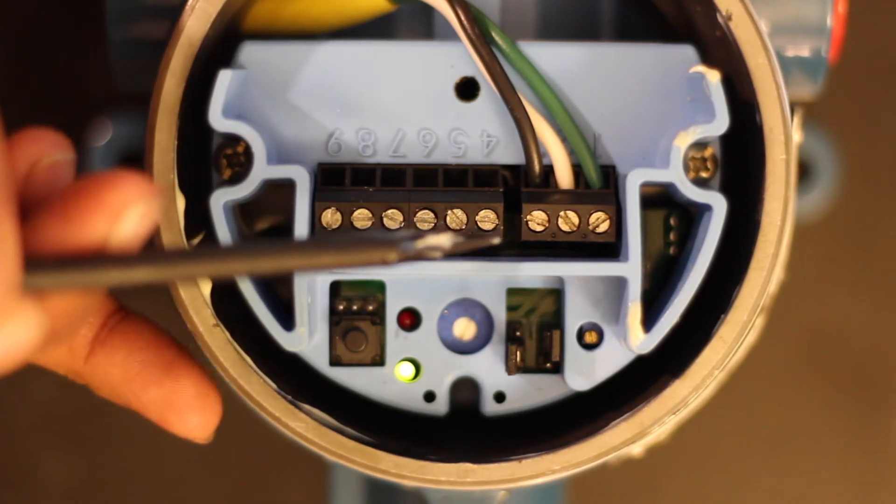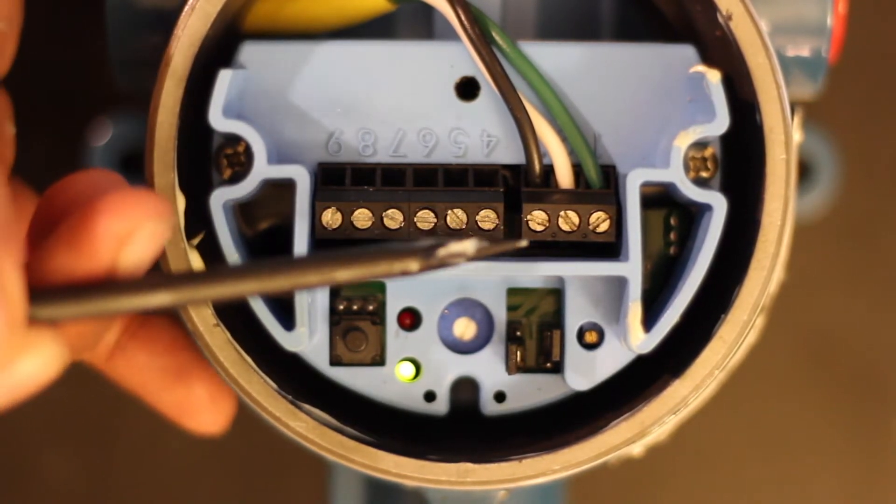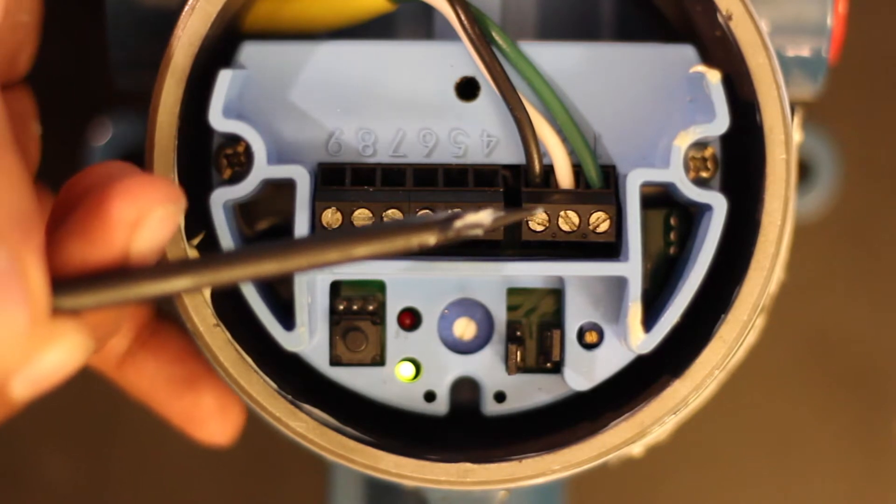You have your universal power supply connections. This particular unit will take in 24 volt DC, 120 volt or 220 volts AC. You have your double pole double throw relay connections from 4 through 9.